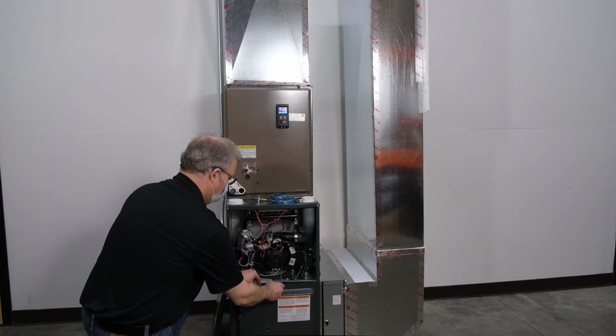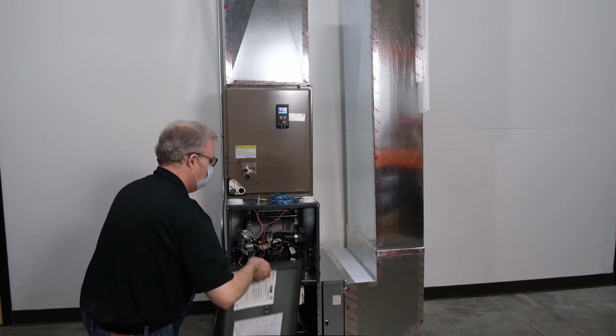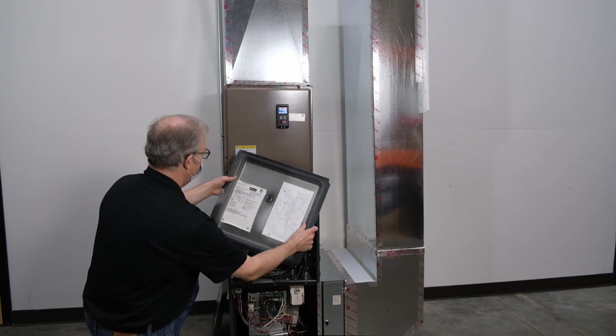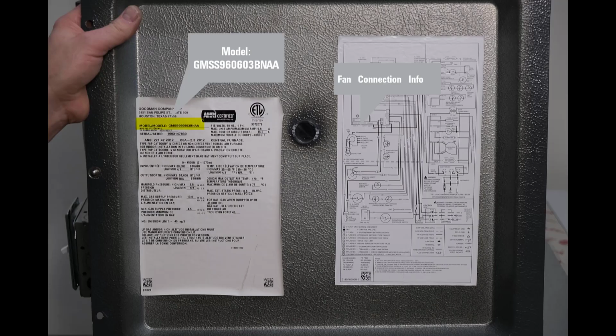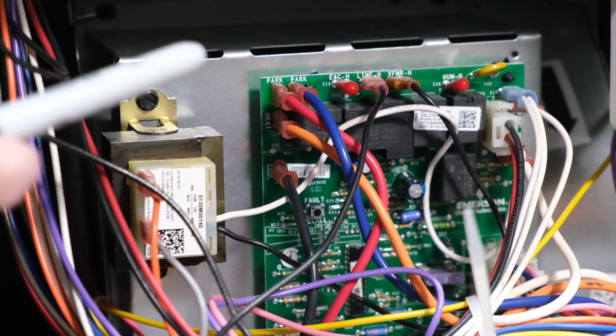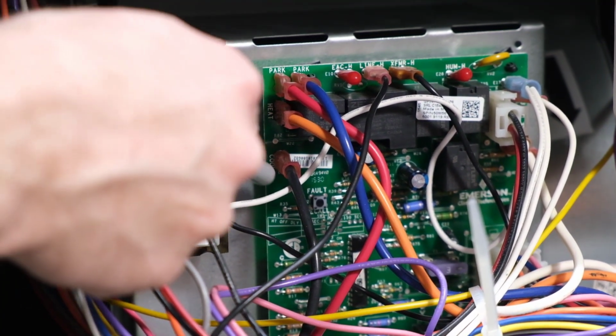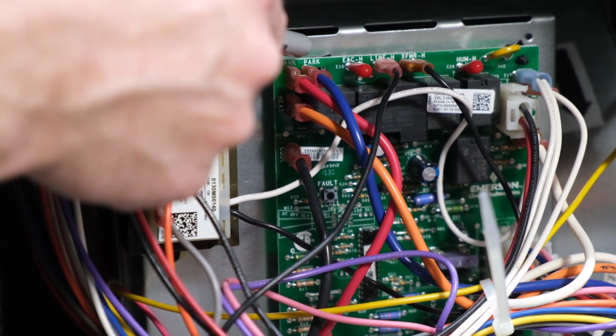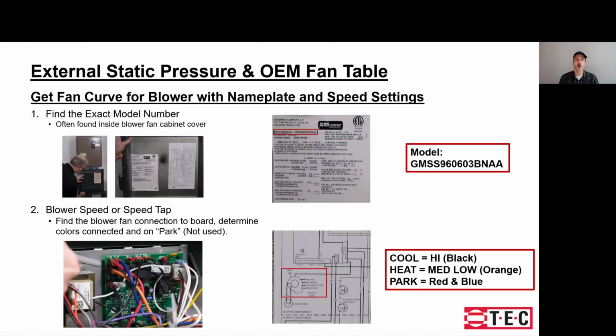Here's Steve taking a look at the furnace, and he's taking the front cover off, which is often where this information is located. On the left is the Goodman model number, and on the right is the fan connection information. Steve will use that information when he's looking at the board where the blower fan is connected to determine what the settings are. You can see that cooling is on black, heat is on orange, and both blue and red are parked.